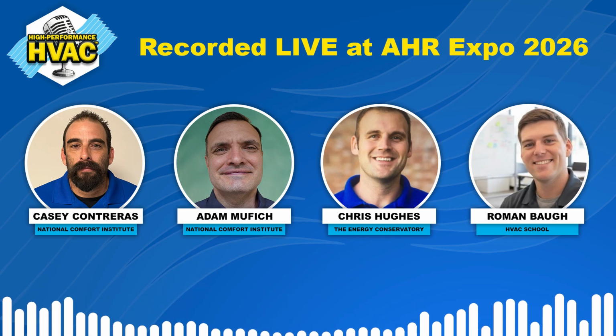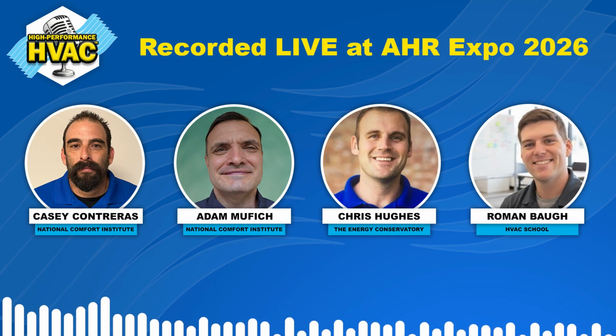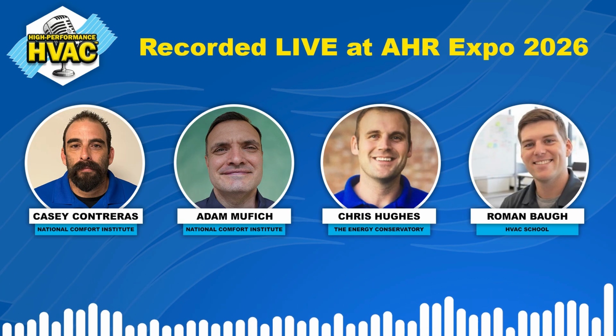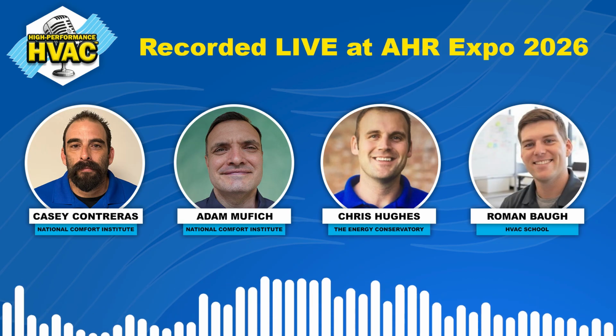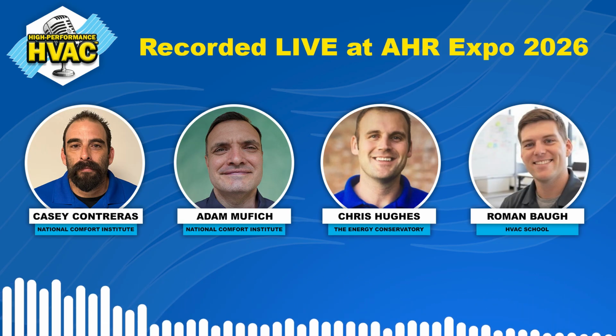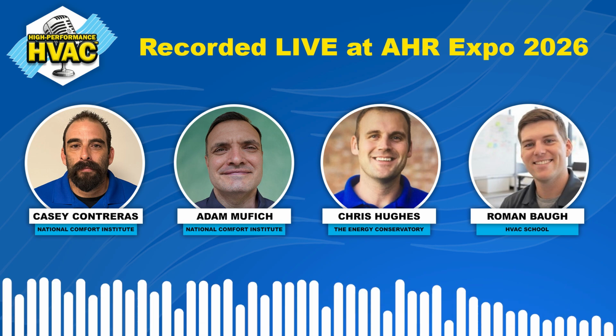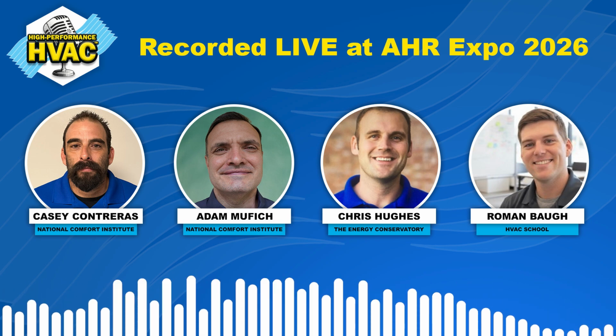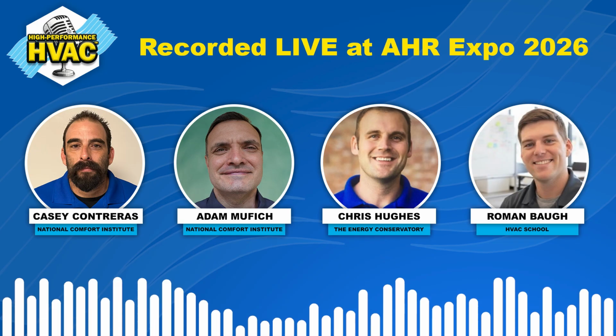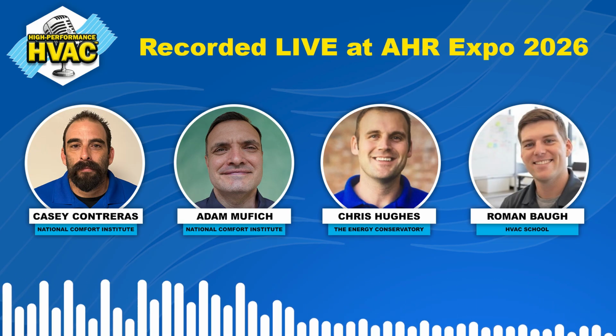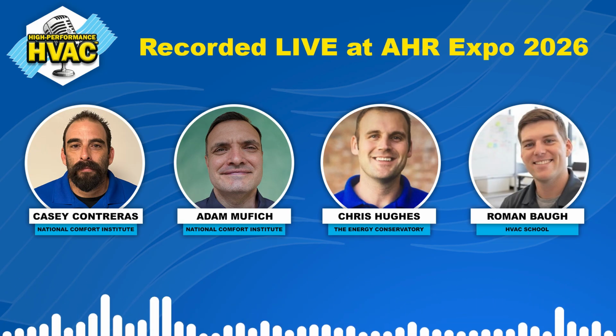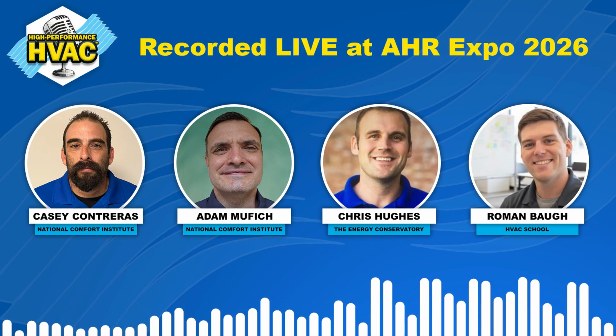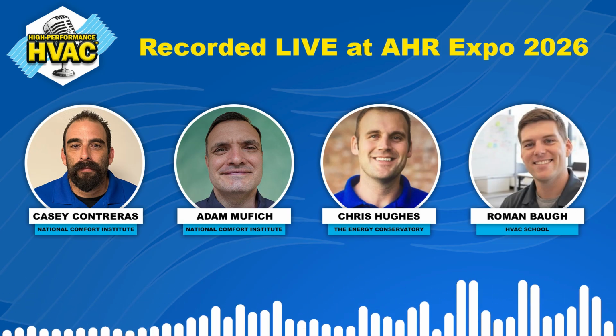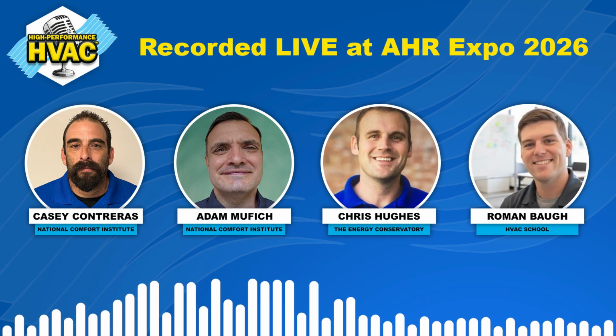Well, I don't know. I have my house, before I came to AHR, it wasn't heating correctly, and I looked at it over Cool Automation to find out that it was actually undercharged. I had trouble maintaining my house last night and heating for some of my zones. And I noticed that when everything was on, my compressor discharge temps went up to like 230, and then it went into low pressure step down, and I was like, well, that's not normal. And come to find out, my unit wasn't defrosting at all, and the reason it wasn't defrosting at all is because it wasn't charged correctly. Let's pump the brakes real quick.